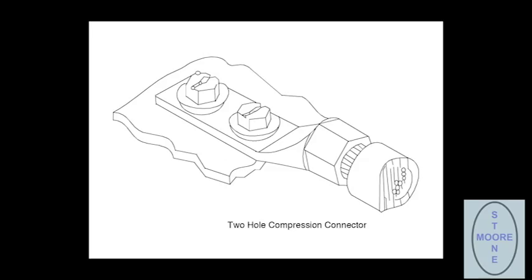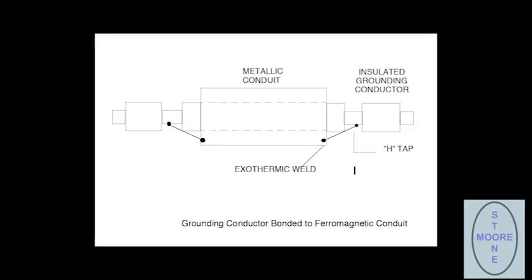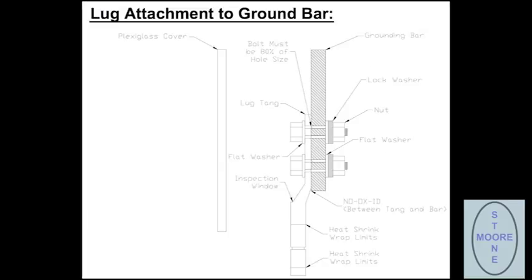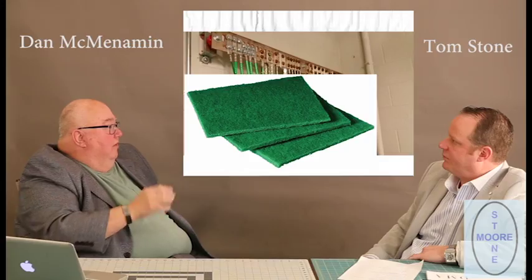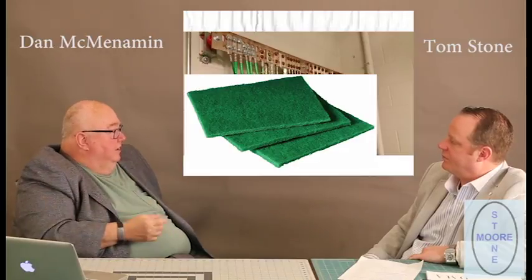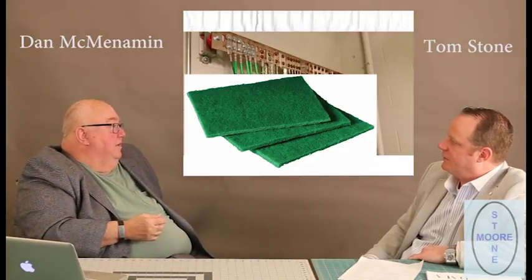How do they connect to the ground bar? I mean, do you lug it or terminate it? Usually they're lugs. Some people use exothermic welds, or some people call them CAD welds. But sometimes they weld to the bar. But it's really better if they use lugs and properly prepare it. If you've got just a plain copper bar and the lugs are placed on there, then they need to clean the bar of any oxides or grime or tarnish, typically with a mild abrasive, like one of those spun plastic scouring pads, like a Scotch-Brite pad. Sorry to use somebody's trade name, but that's really the best tool for that.